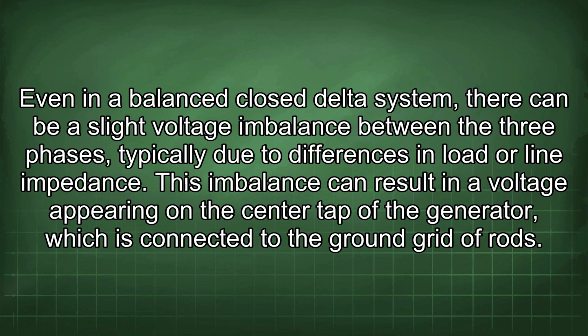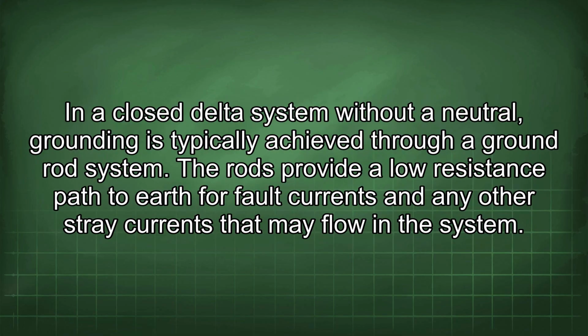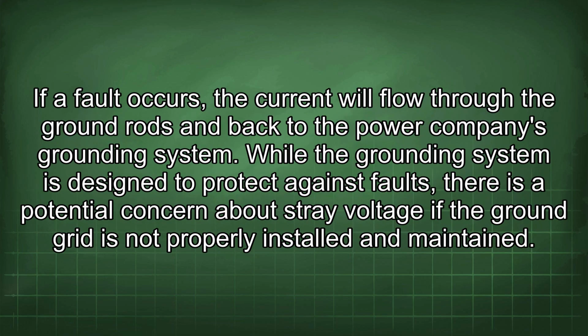This imbalance can result in a voltage appearing on the center tap of the generator, which is connected to the ground grid of rods. In a closed delta system without a neutral, grounding is typically achieved through a ground rod system. The rods provide a low resistance path to earth for fault currents and any other stray currents that may flow in this system. If a fault occurs, the current will flow through the ground rods and back to the power company's grounding system. While the grounding system is designed to protect against faults, there is a potential concern about stray voltage if the ground grid is not properly installed and maintained.